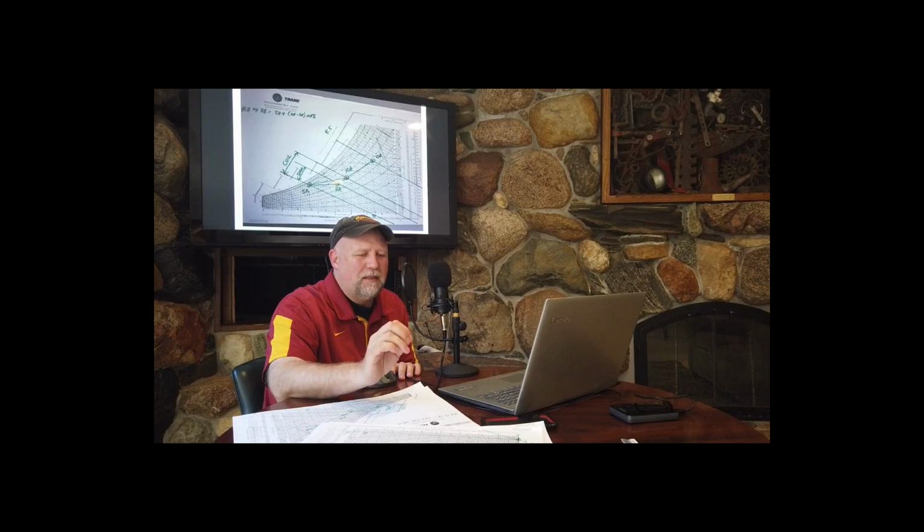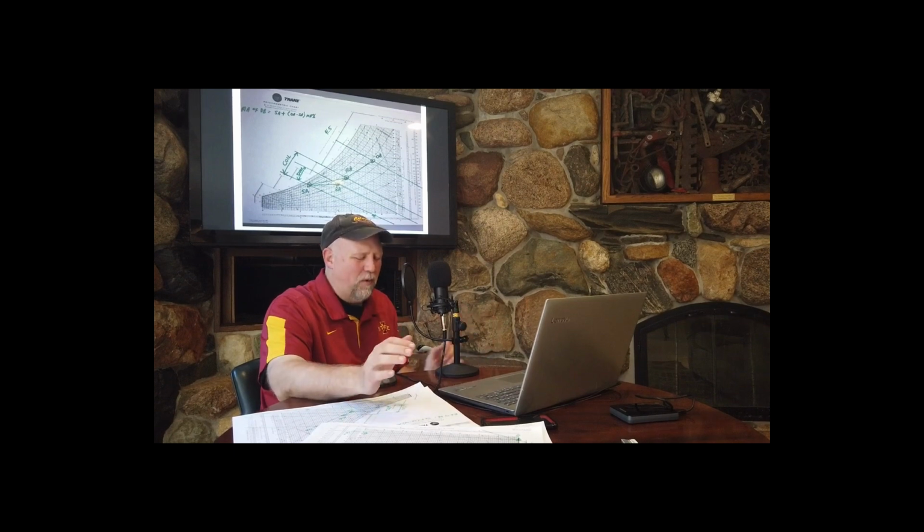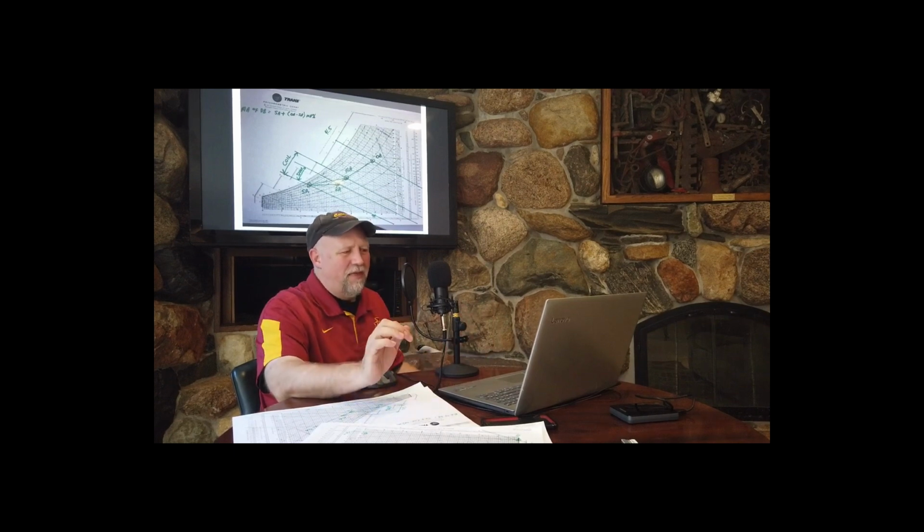On most buildings, the amount of outside air that we bring in should be just slightly greater than the amount that we're exhausting. That gives a building a positive pressure. But for this class, we are making a simplification, and that simplification is that those two airflows are the same. Exhaust air CFM equals outside air CFM.